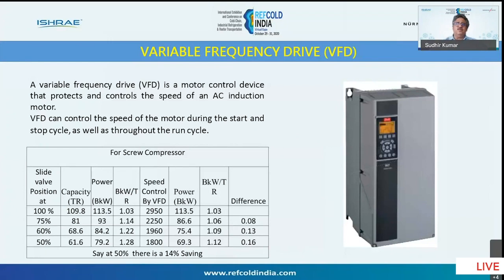Of course, there is one small disadvantage of using a VFD system. The major expense you will incur is that you'll have to have a harmonic filter, because sometimes it will disturb the harmonics of your other equipment. So while designing a refrigeration plant with a VFD drive, you should take care of harmonic filters also.